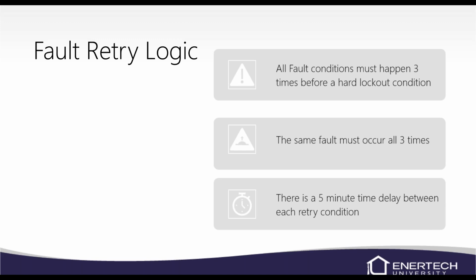Now it's got to be the same fault all 3 times. If you have 2 high pressure faults and then the third is a low pressure fault and then it runs fine, the unit will just keep running. It has to be the same 3 times, 3 high pressures, 3 low pressures, what have you. And again, there is a 5-minute delay in between each retry.